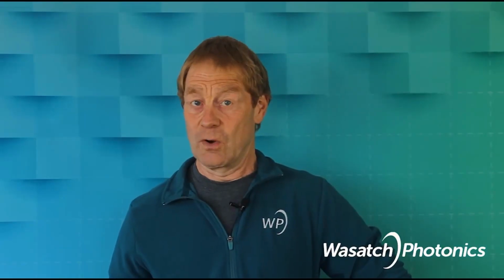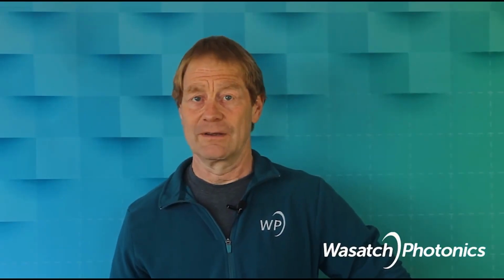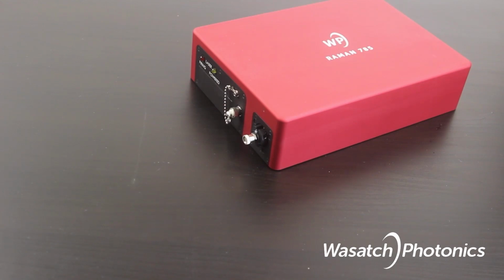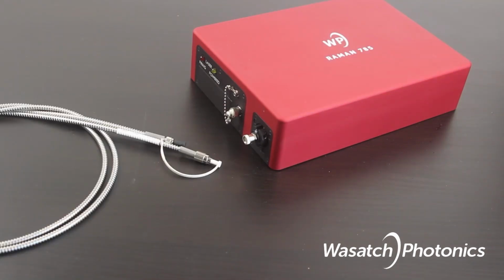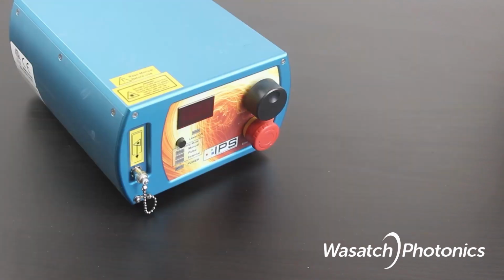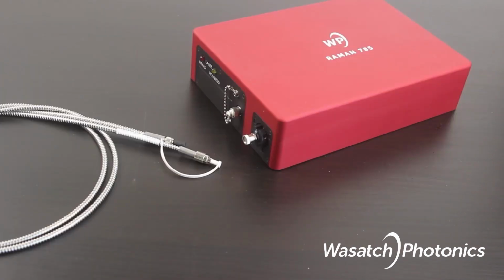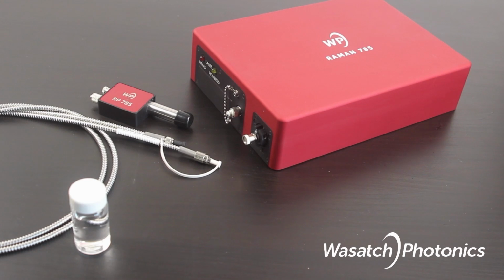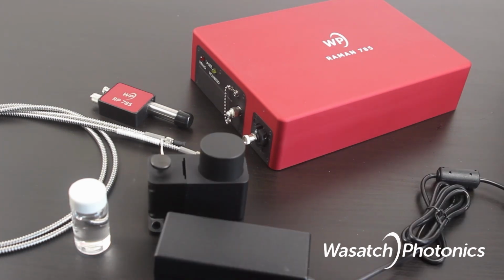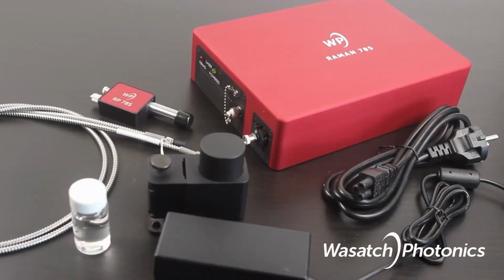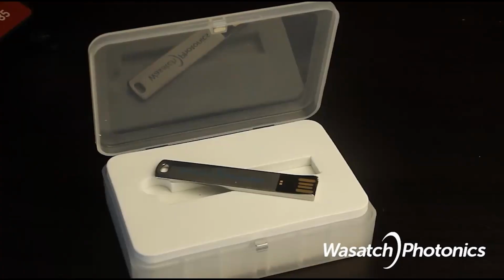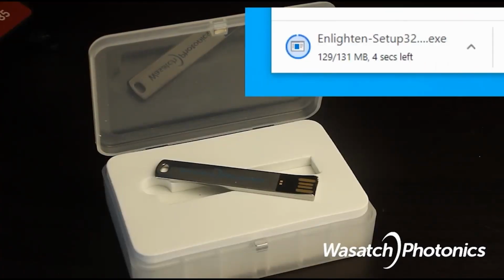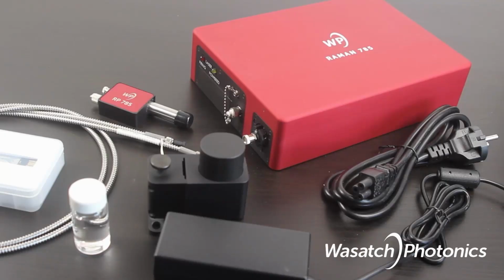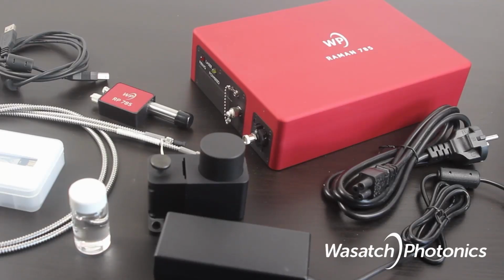To do a measurement with your Wasatch Raman system, you'll need the following. Your spectrometer, well, of course, optical fibers, a laser, and usually that is built right into the spectrometer. If it's not, then the laser is a separate instrument. Then you need a Raman probe, a Raman sample, sample holder, power supply, a power cord with a plug that matches your location, the software, either from the USB stick that came with the spectrometer or as a download from the website, a USB cable, and finally a PC.